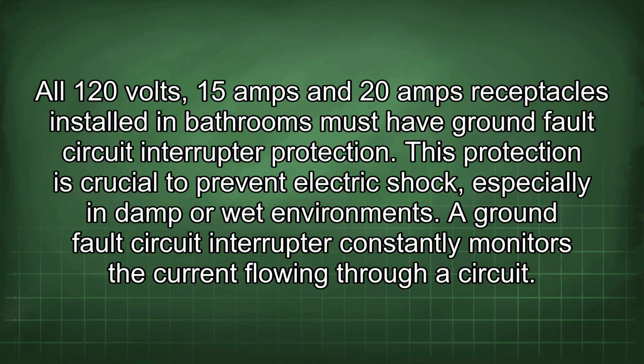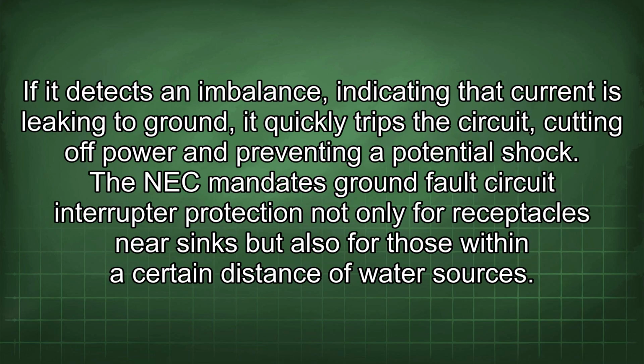All 120 volt, 15 amp and 20 amp receptacles installed in bathrooms must have ground fault circuit interrupter protection. This protection is crucial to prevent electric shock, especially in damp or wet environments. A ground fault circuit interrupter constantly monitors the current flowing through a circuit. If it detects an imbalance, indicating that current is leaking to ground, it quickly trips the circuit, cutting off power and preventing a potential shock.